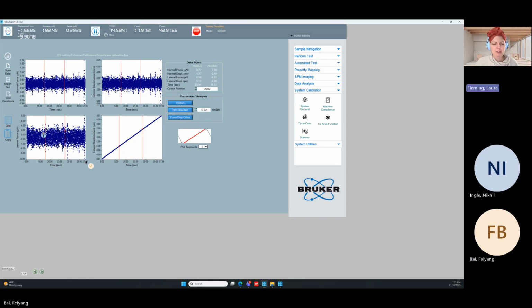Well, from an instrumentation perspective, ground floor means sitting on the ground, which is not the case here. If you are on the second floor from the other direction, think about something sitting on the earth. There's all this earth that is very inert and it dampens out vibration. Versus if you're on a floor with a room below you, you're basically sitting on a drum head, which means that vibrations travel much more easily through the floor and into your instrument. So things to consider. If you can move it to a quieter place, that might be better.